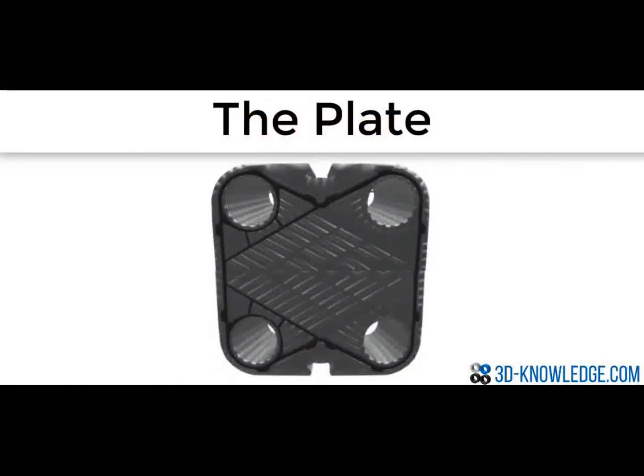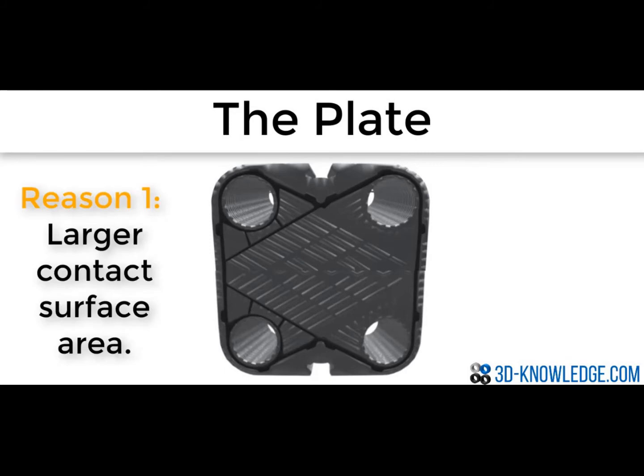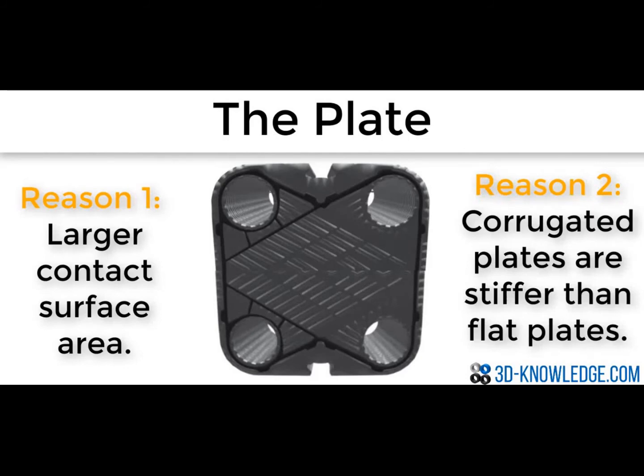You may have noticed that the plate isn't flat, it's actually corrugated. The reason for this is threefold. The first reason is that a corrugated plate gives a larger contact surface area, and this increases the heat transfer rate and makes the heat exchanger more efficient. The second reason is that a corrugated plate is actually stiffer than a flat plate, so you can manufacture a thinner plate, and this thinner plate has a higher heat transfer rate than a thicker plate. The third reason is that the corrugated plate creates turbulent flow.